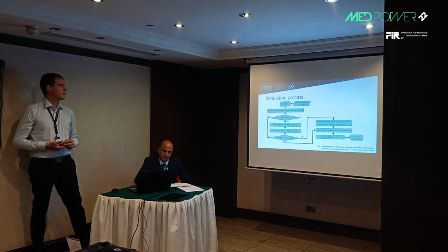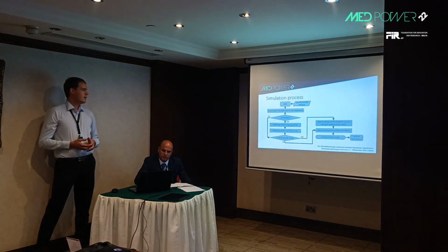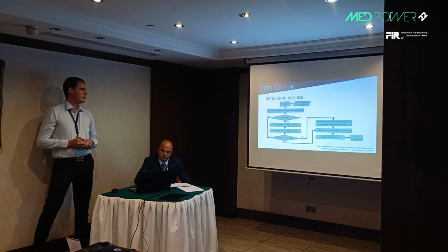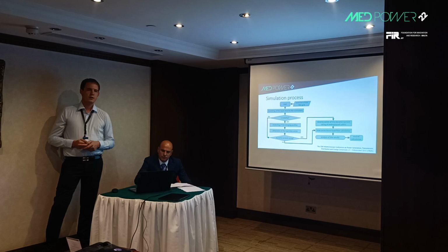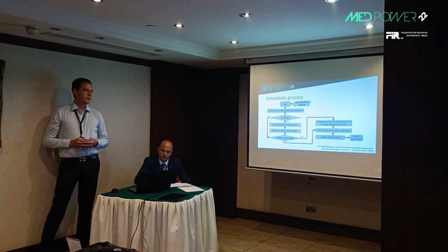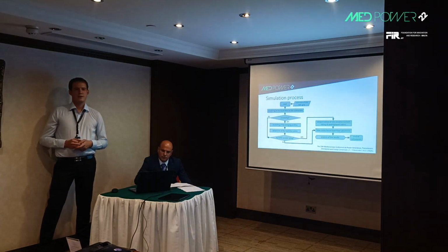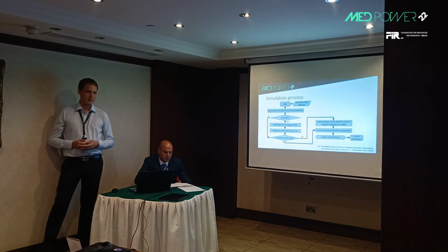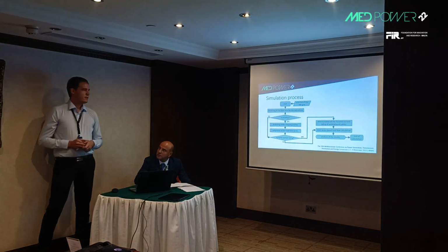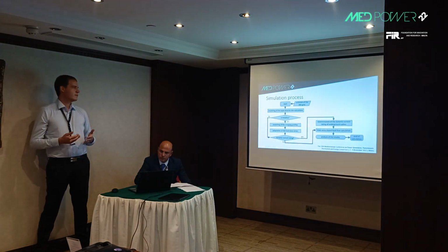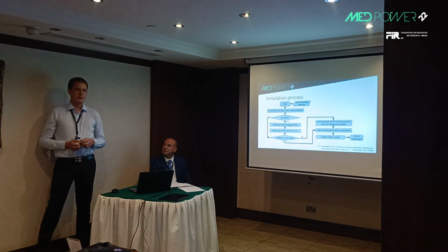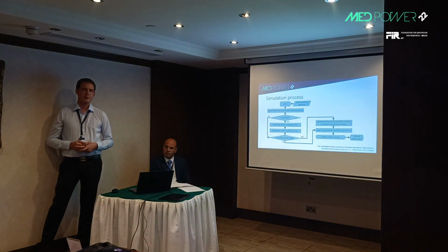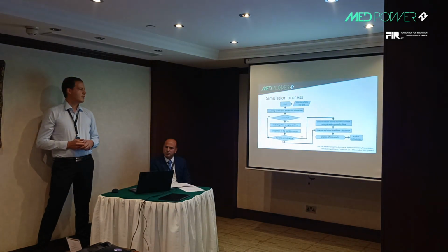And if you want to analyze e-mobility, then we must model the charging profiles. And for this we have a trip-based model. This model uses driving profiles, and with the battery capacity of the cars, then we can model the charging profiles, and the charging profiles and how many EV vehicles at each substation we have. So we can now calculate a new time series.